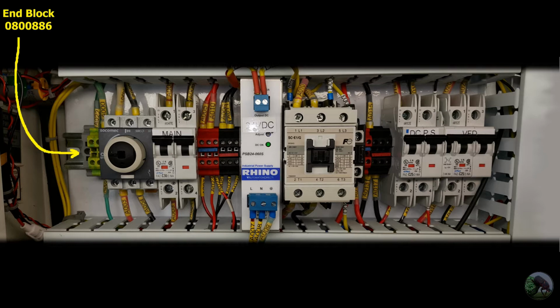So anyway, moving on, the next up is this grounding block. So these are colored yellowish green kind of mix. And the important thing about this part is that there's two little metal hooks that touch the DIN rail, and so they essentially make an electrical connection with whatever wires you're putting in. They make continuity with the DIN rail, which then makes continuity with the back plate and the chassis of your machine. And so you can't really interchange these, even though they look very similar to, say, these red or black terminals. They're very different in that regard because they're making continuity with the chassis of your machine. And so pretty important difference there.